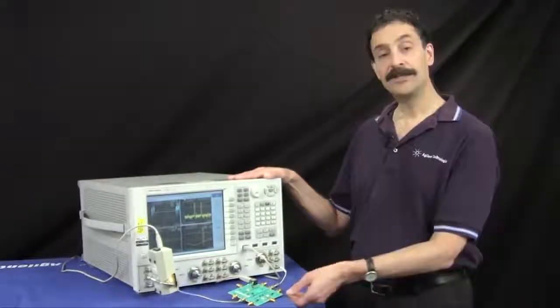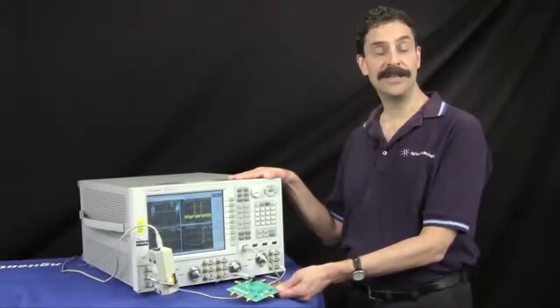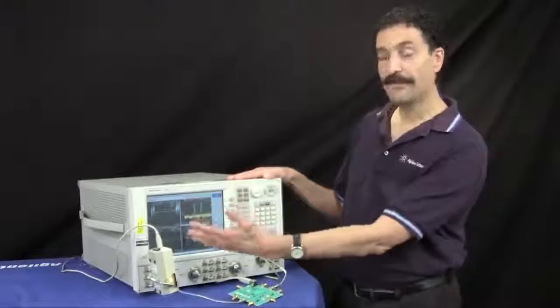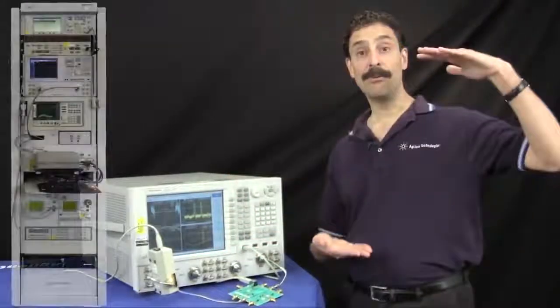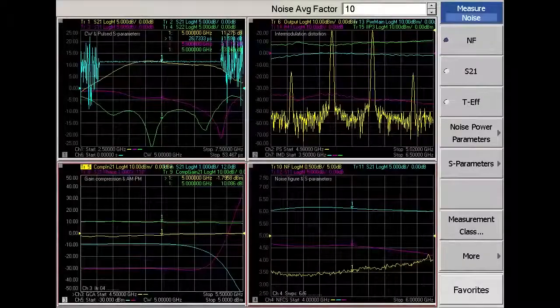With a single set of connections to a device under test, or DUT, the PNAX is capable of performing many RF tests that used to take a rack of test equipment. Measurements include S-Parameters, gain compression, intermodulation distortion, and noise figure.